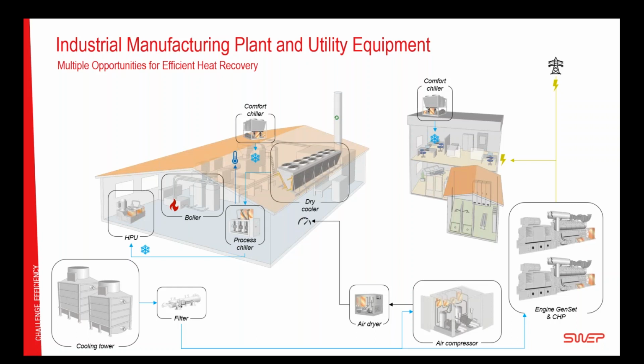For the process chiller, there is a dry cooler. Since it's a closed system, there is no need for the filter. And at this point here, I would like to, so to say, pause a little bit and just see. This is a fairly typical installation. There is a lot of applications. Everything might be as energy efficient as it can be. Each producer of the machinery has worked to make their system efficient, but there is still a lot of waste since there is no energy recovery. And now that is what we will start to build into this system.